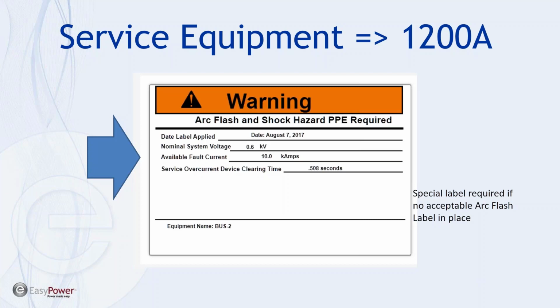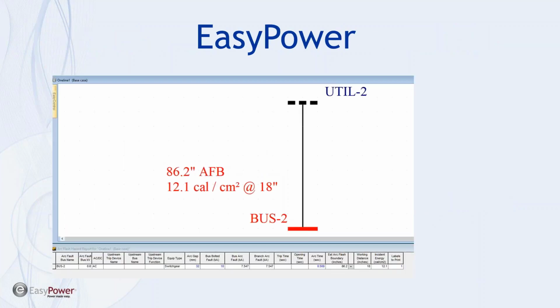Now this again is not required if there's an arc flash label there, which means there's already been a study. If we run these values through EasyPower, we see that we calculate just over, looks like, 12 calories per square centimeter. And what I want to do is take these same values.